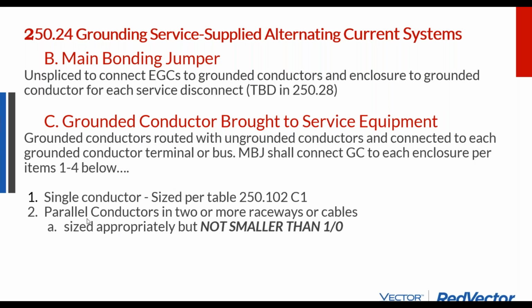So here's another kind of side note. Parallel conductors in 2 or more raceways should not be smaller than 1/aught cable. So this is a different instance, but cable is rated for so many amperages, 20 amps, 40 amps, 60 amps. Once you start getting into utility conductors, they start getting thicker and higher amperage. At some point, you may say, well, is it easier to buy and pull and install 2 smaller wires than 1 big, thicker wire?